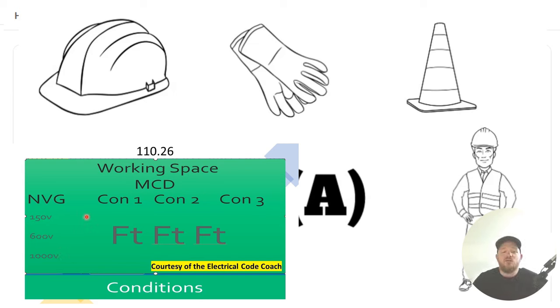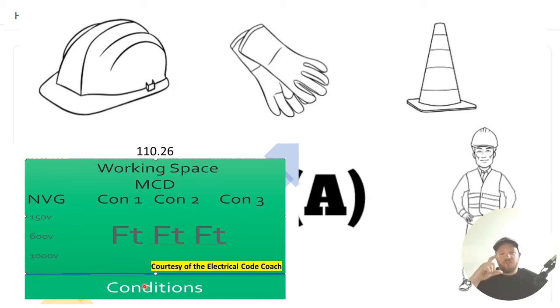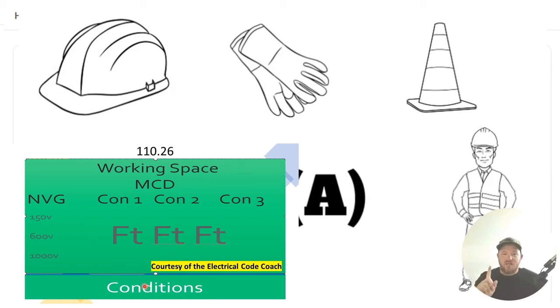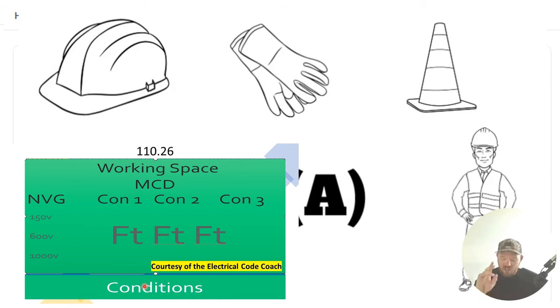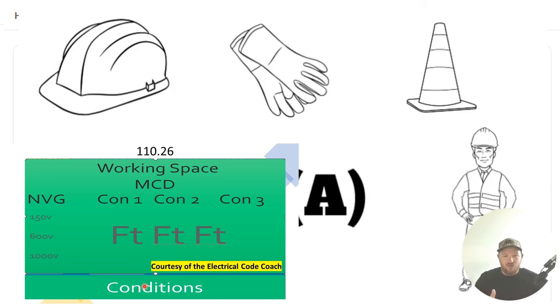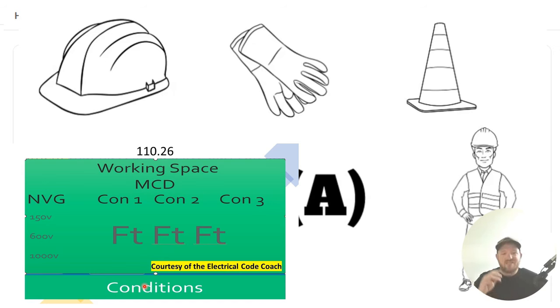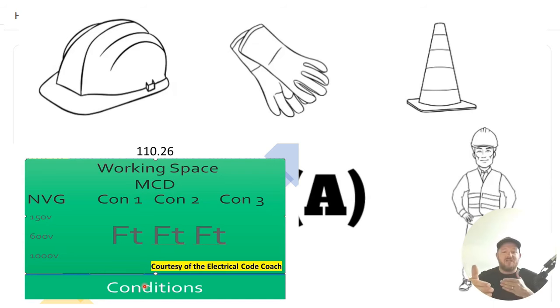Then we need to come deal with this condition business. Now, down at the bottom is going to list your conditions below this table. Condition one is if there's exposed live parts on one side. Condition two is if there's exposed live parts on one side and there are grounded parts on the other side, like a block wall or something like that. And then condition three is going to be if there are exposed live parts on both sides.